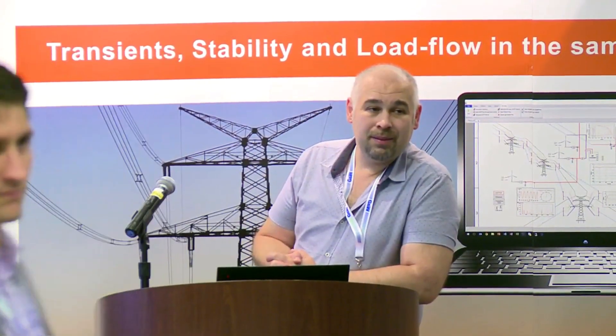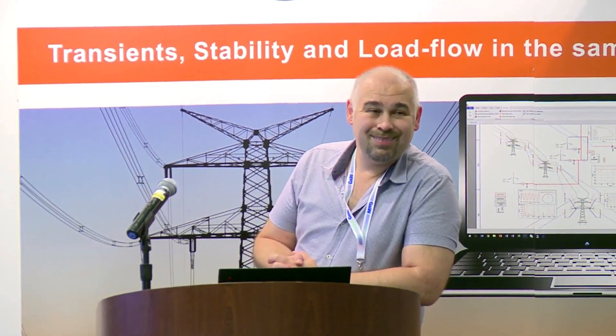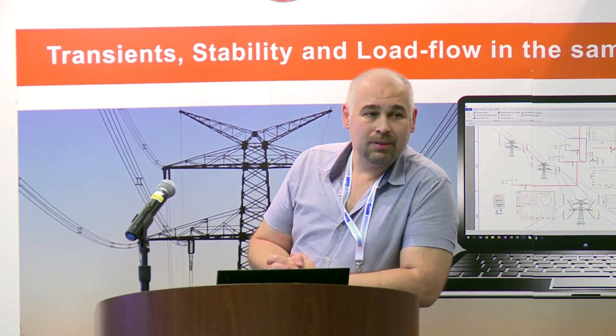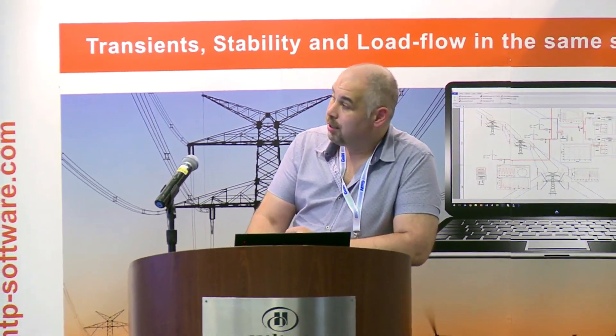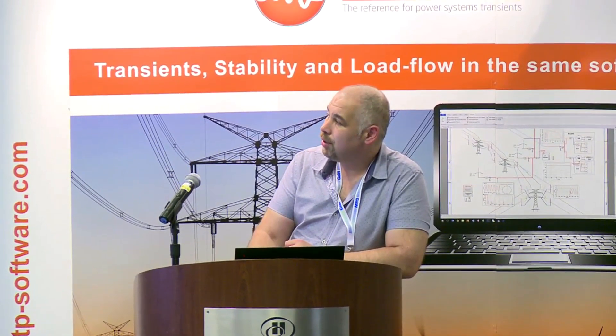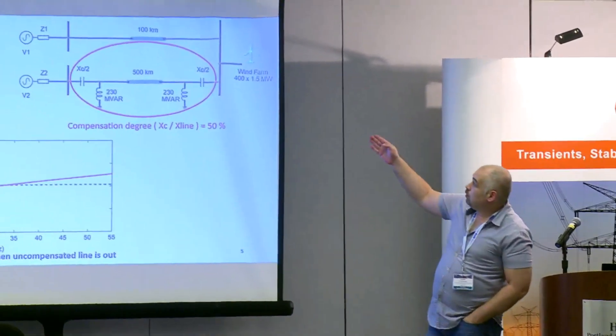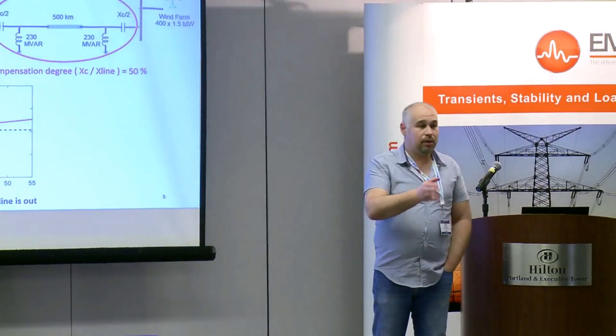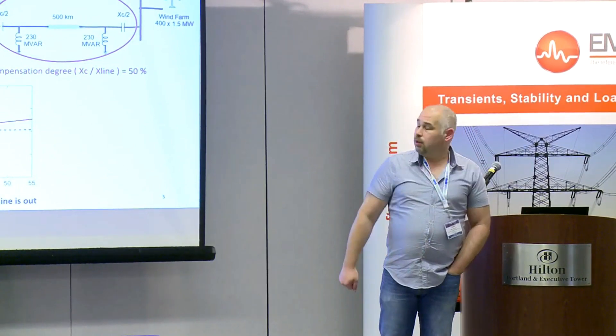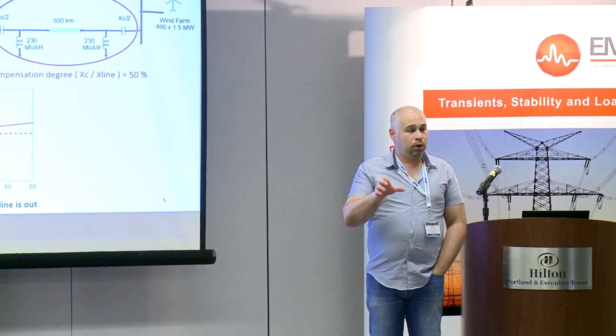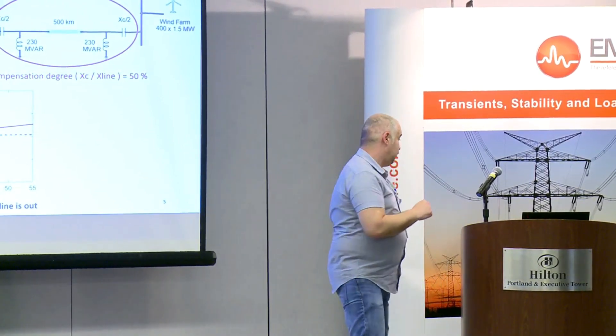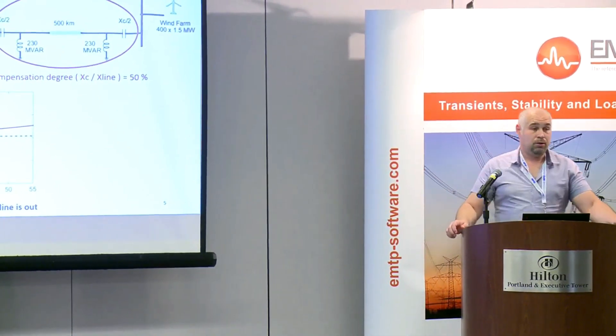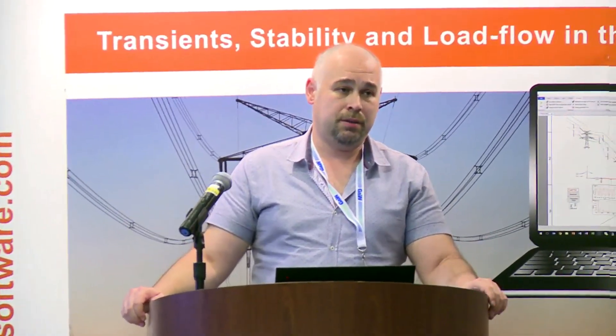Q&A: When modeling the wind turbine for the control interaction study, the internal network is included with cable representation using PI sections. The wind park is connected to the transmission system via transformer, with the internal cable network aggregated and represented with PI sections.